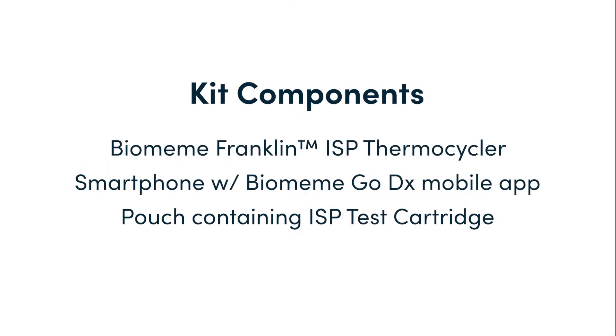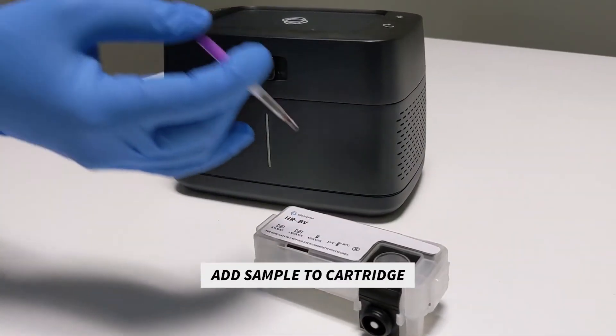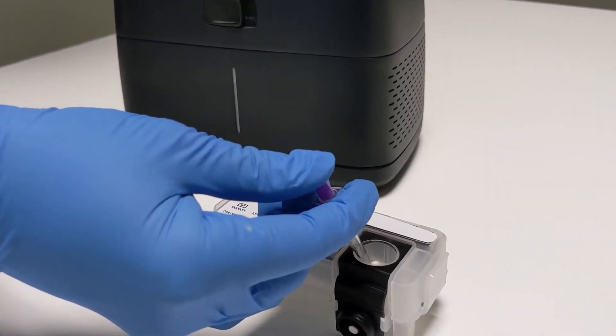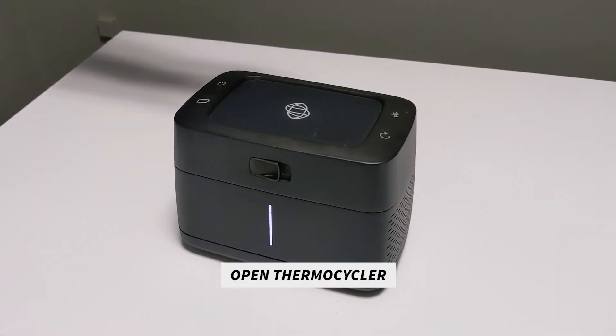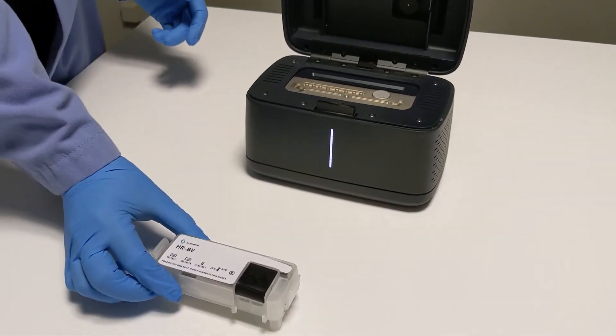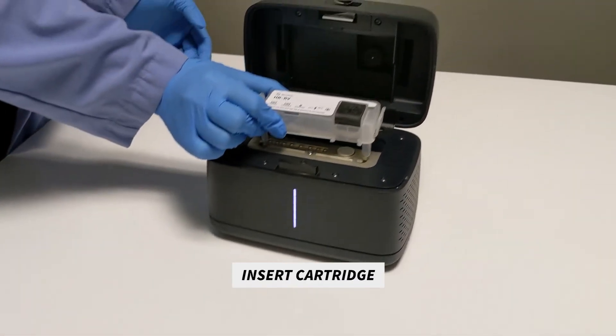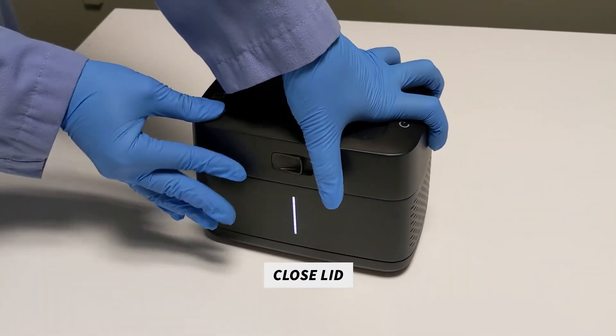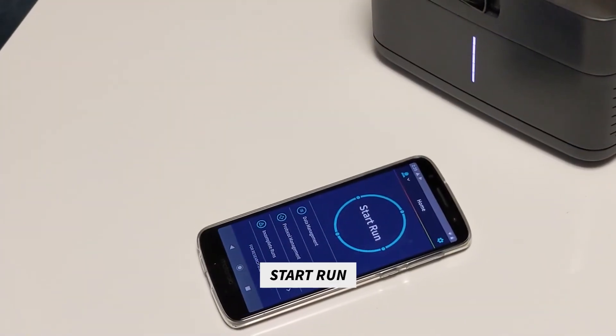We'll start with Biomeme's first-generation automated thermocycler with integrated sample prep, called Franklin ISP. Step 1 is to gather the handful of items required to run a test. This includes a Biomeme Franklin ISP thermocycler, a smartphone with the Biomeme Go DX mobile app installed, and a pouch containing a single-use ISP test cartridge. You start by carefully transferring sample into the ISP test cartridge — in this case a drop of blood — and then gently close the rubber lid on the cartridge. Next, we open the lid of the Franklin ISP thermocycler by sliding the latch on the front of the unit to the right, and we insert the closed ISP test cartridge. We close the lid on the thermocycler and tap Start Run in the Biomeme Go DX mobile app.